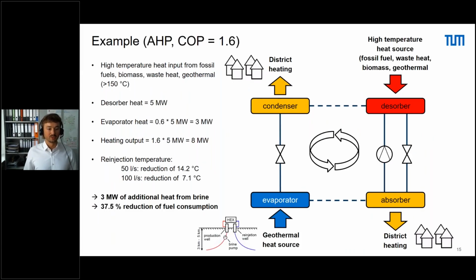In a practical example, it would look like this. The high temperature heat input in most cases would not come from geothermal, but from other heat sources, for example, fossil fuels, biomass, waste heat. And imagine we have a peak load of 8 megawatts that we have to cover. Now we can only use 5 megawatts from the fossil fuel, for example, to get 8 megawatts of heat output. That's because we can extract additional 3 megawatts with the evaporator from the geothermal brine. And that would translate to a reduction of fuel consumption of around 37.5% and a reduction in reinjection temperature: at 50 liters per second, that would be 14.2 degrees Celsius, and at 100 liters per second, it would be 7.1 degrees Celsius. So this technology might be very interesting for projects where we have fossil burners right now, which are used to cover peak loads. So that's why we look also into that.